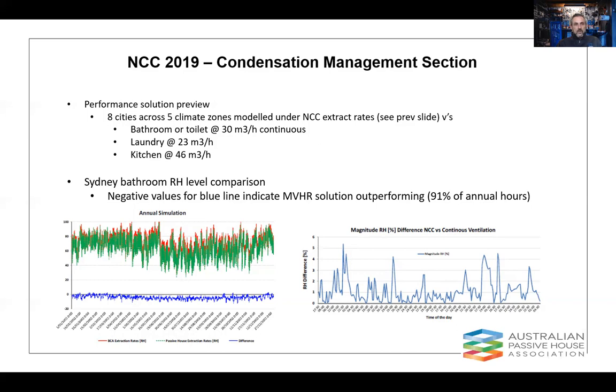And I've shown you just a quick snapshot there of Sydney outcomes. It's a little bit difficult to follow, but red and green are the 2 different ventilation rates there. The passive house is the green one, NCC is the red, and what we're showing on the vertical axis is relative humidity, and on the horizontal axis is the 365 days of the year. And what you can see there, the blue line at the bottom is the difference between the 2. So that's below 0, which is a good thing for us with MVHR units, because it's saying that whenever this is below that 0 line, the relative humidity under the MVHR solution is better than the NCC.